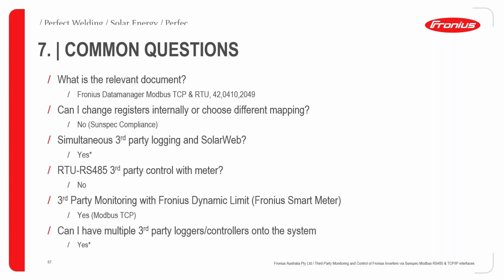The Fronius meters speak on the RS485 channel, and we're actually using that for the control or monitoring. It depends how you use it, but you actually can't have them both. Now I'd like to address the question: can you have multiple masters on RS485? You can't, because it's not meant for that. If you have multiple masters, whenever either of the masters is busy, that will render the channel useless. Plus, the slaves will be confused about when and where to respond. So it's definitely a less than ideal situation.